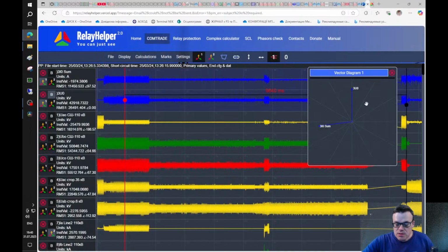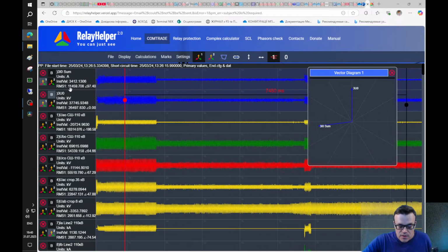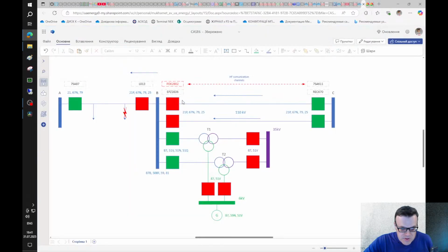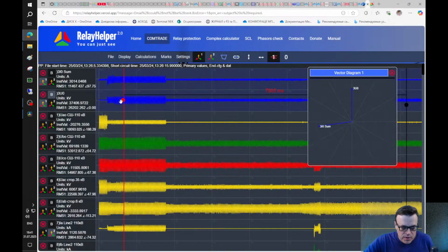So I put together a summary. If we calculate the zero sequence current and make the zero sequence voltage the base channel, then for a short circuit on the protected object the zero sequence current should lead the zero sequence voltage by 90 degrees, something around that. This value is very big, and we checked the settings of the zero sequence overcurrent ground protection. From that period of time, on the substation B side, 3 steps of overcurrent protection should have tripped.